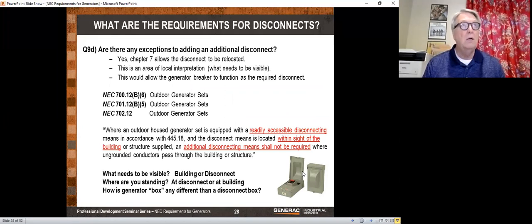So there are some jurisdictions in the country that actually want a switch or a circuit breaker between the generator and the transfer switch where it goes into the building. But thankfully, none of them are here in the Rocky Mountain area. And so if a local code requires that, that could be an issue, but it's pretty rare. But we have seen it, particularly in some of the bureaucratically intense cities.